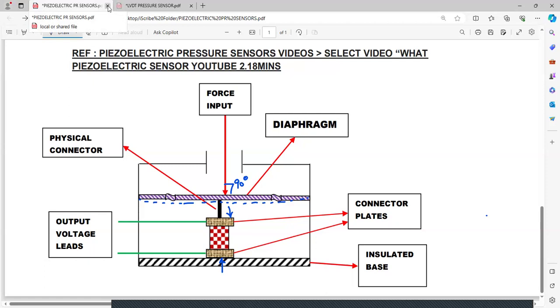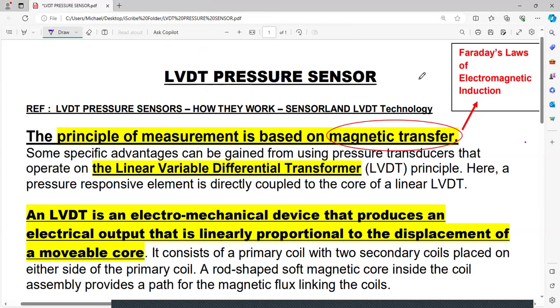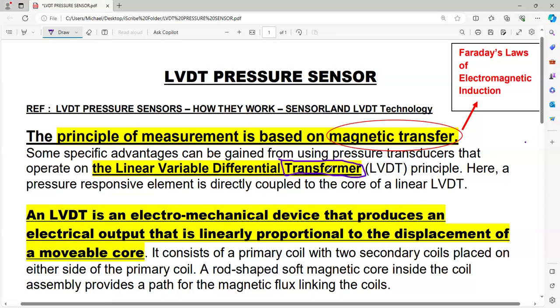LVDT pressure sensor. If you ask what is an LVDT pressure sensor, LVDT stands for linear variable differential transformer. Sometimes the word transformer is replaced by the word transducer. Really speaking, it is not a transducer, but we will keep the term transformer because we have just completed the topic of transformers.